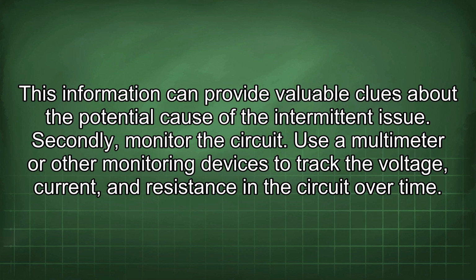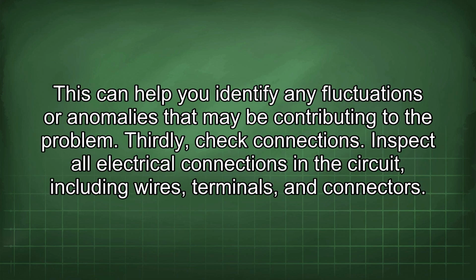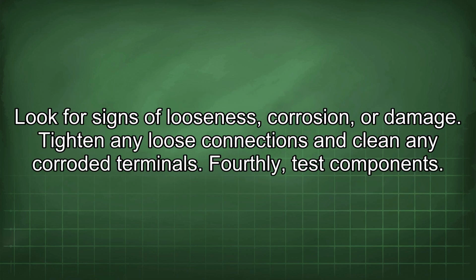Secondly, monitor the circuit. Use a multimeter or other monitoring devices to track the voltage, current, and resistance in the circuit over time. This can help you identify any fluctuations or anomalies that may be contributing to the problem. Thirdly, check connections. Inspect all electrical connections in the circuit, including wires, terminals, and connectors. Look for signs of looseness, corrosion, or damage. Tighten any loose connections and clean any corroded terminals.